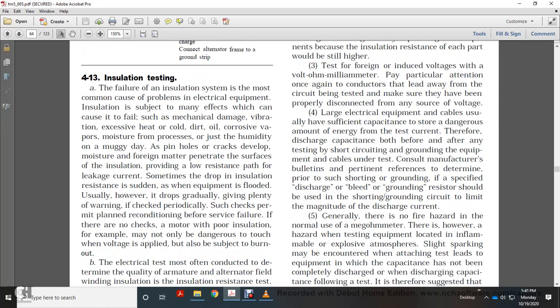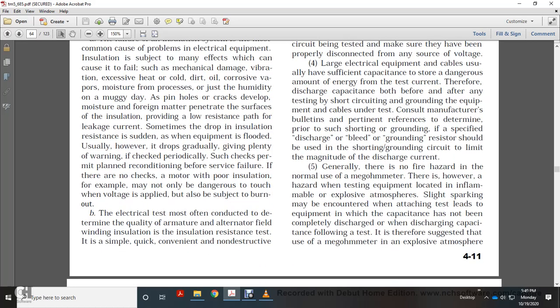For discharge capacitance, before and after any of the testing, short circuit and ground the equipment and cable, following the manufacturer's bulletin for the pertinent reference. Prior to starting the shorting of the grounding, a discharge bleeding ground resistor should be used in a shorted ground circuit to limit the magnitude of the discharge current.